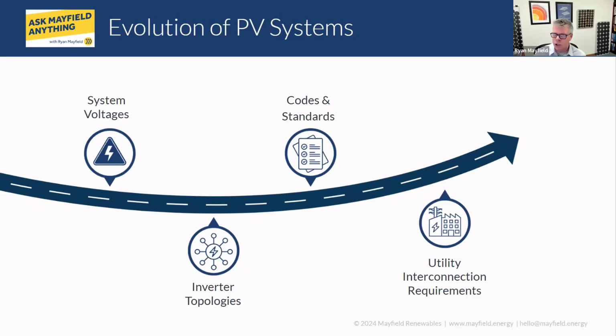But the way the ground fault protection would work is across a fuse. On small systems, I forget what the cutoff was, maybe 30 kilowatts, somebody can correct me if I'm wrong, there was a power cutoff where that ground fault protection fuse would be 1 amp for small systems and actually up to 5 amps on larger systems. And so our ground fault protection now is much more sensitive, and it will catch potential ground faults that maybe you didn't catch before. I'm curious for you guys about the arc fault protection. What are you seeing in terms of that and these new inverters on these old systems? Is it creating any sort of problems?